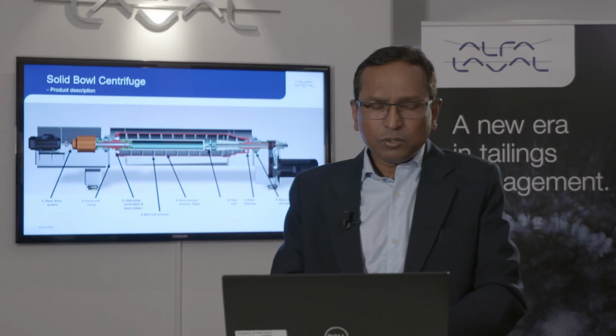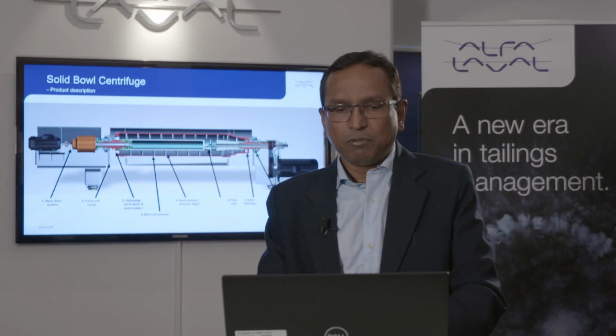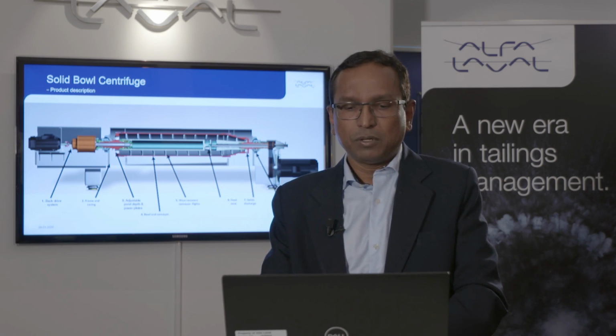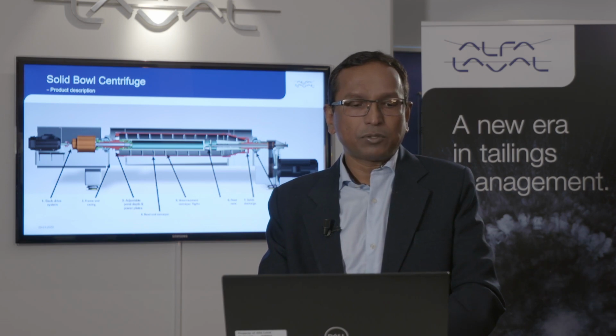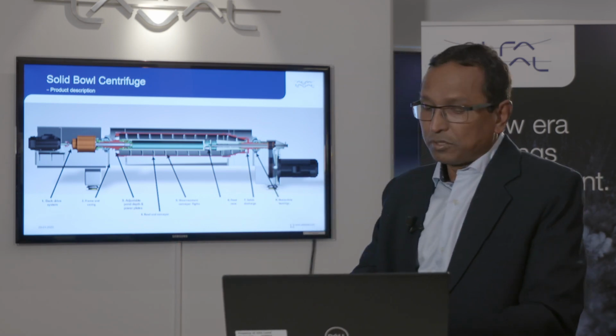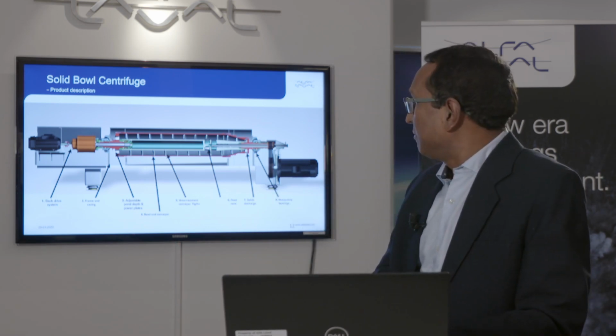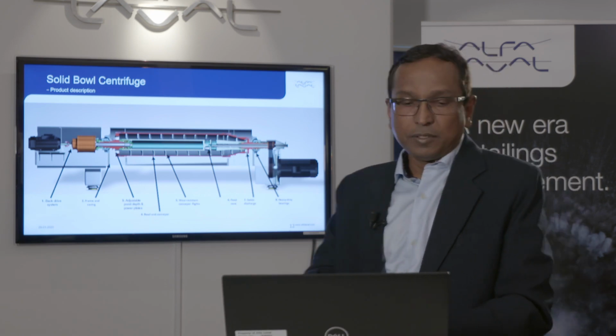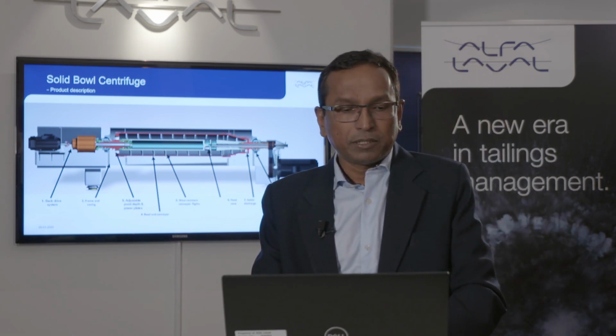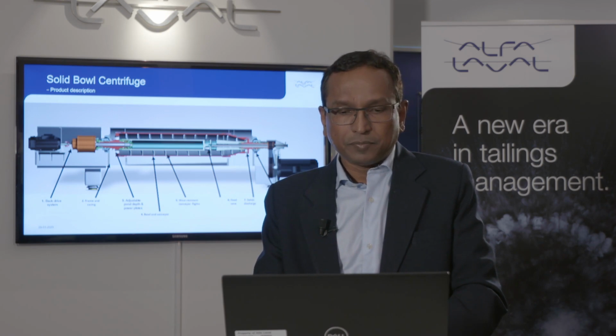So this centrifuge has one main motor, which is shown on the right side or towards the feed tube, and it also has a smaller motor called the back drive motor, which is used for rotating the conveyor, and there's a gearbox in between.